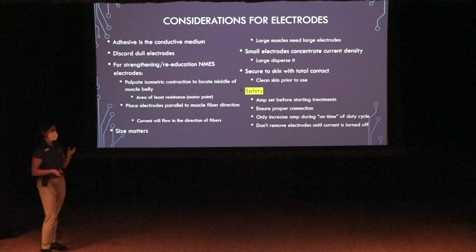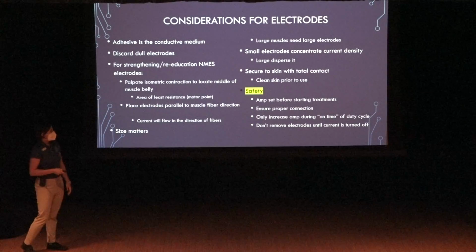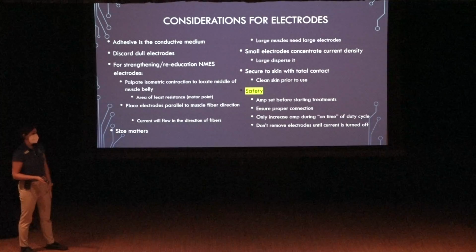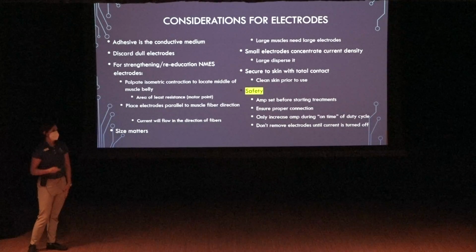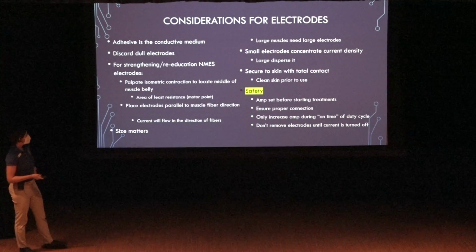That should be about 8 to 10 uses. I know we can't throw out an electrode every time we use it, but it's going to lose its conductance, and you might actually burn or hurt the patient if you keep using the same electrode for months on end. So if you can, throw them out after 8 to 10 uses.